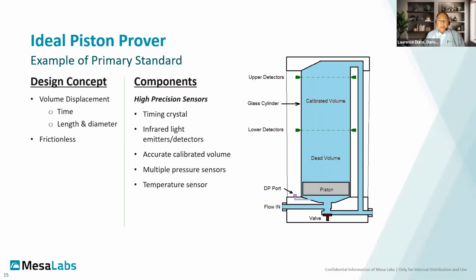Very high precision. As you can see on the right side, you've got a valve at the bottom. In its normally open position, the air or gas just flows right through. The valve closes, it introduces your air or gas under the piston. Piston goes up, it trips a lower detector, which starts a timer, upper detector, which stops the timer, and then also trips the valve back open to allow the piston to fall back.